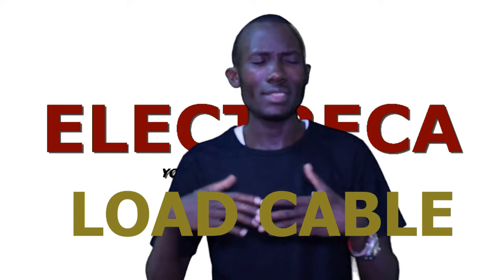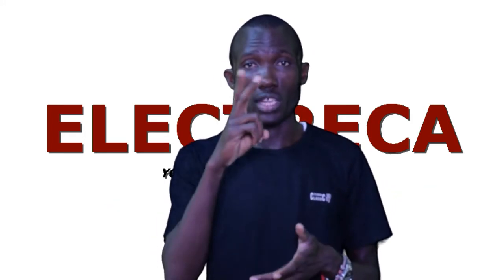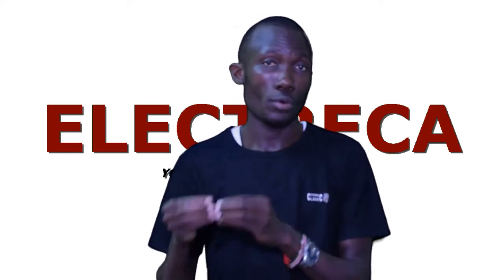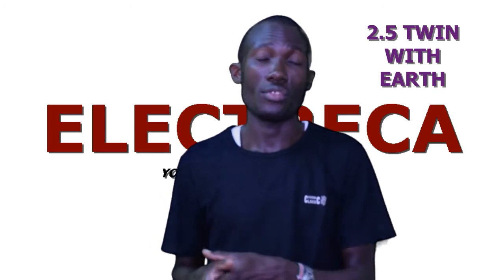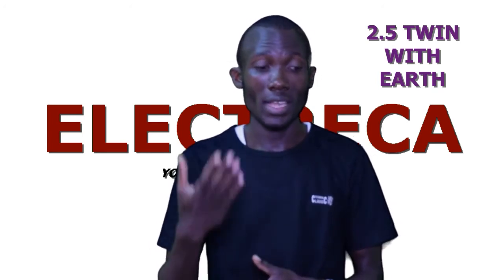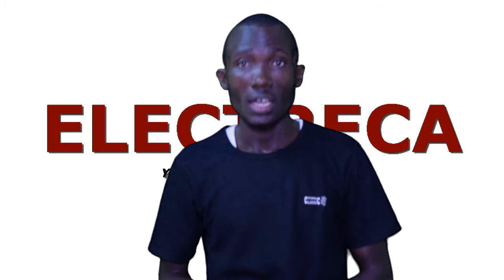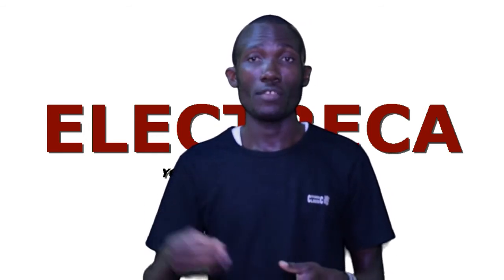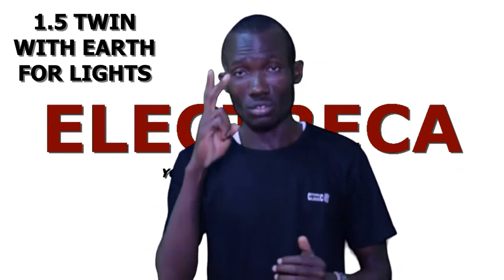Now, we all know that in installation, in most cases, we use two types of cables. And when I'm saying types, I mean in the thickness. So first, for sockets, we always use 2.5 twin with earth. That 2.5 will be supplying all the sockets in your installation, except the cooker socket, that will vary. Now, you also have lights that you will take 1.5 twin with earth. Those are two types of cable.